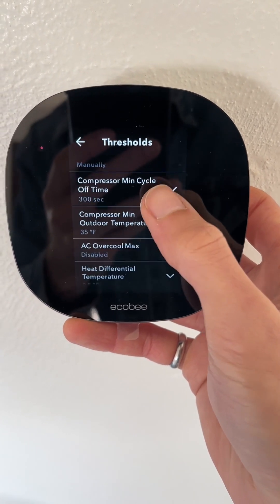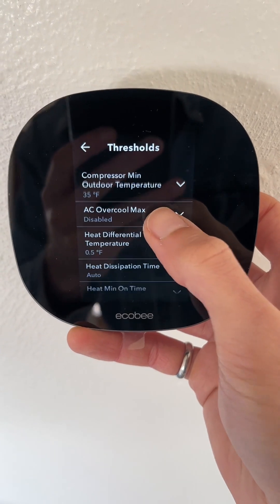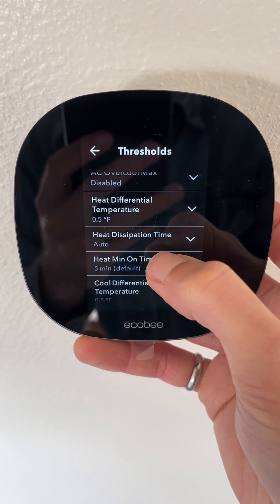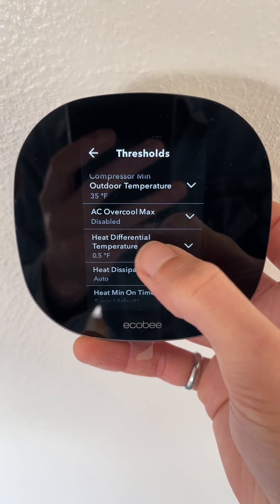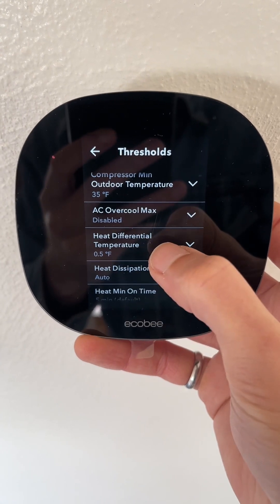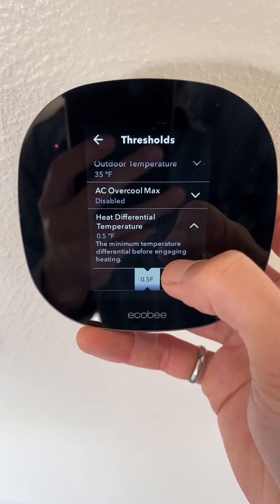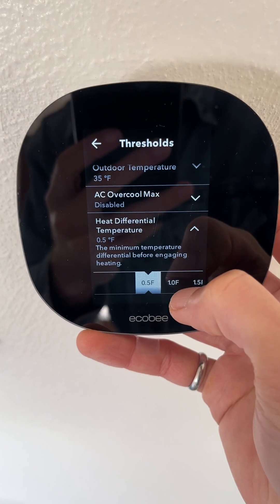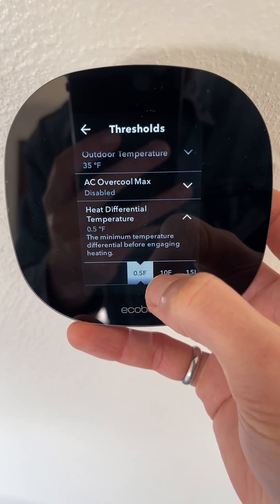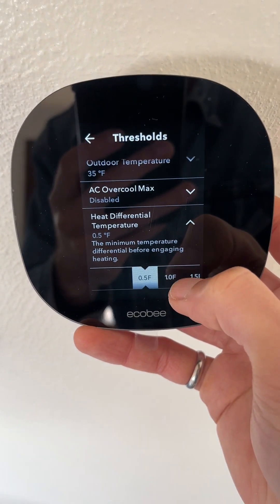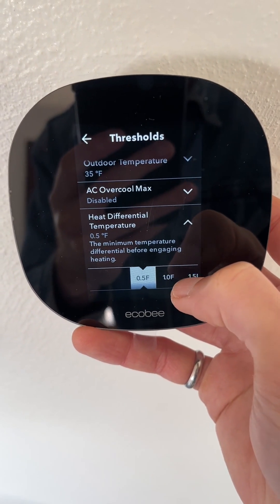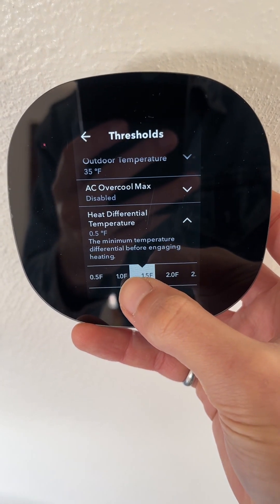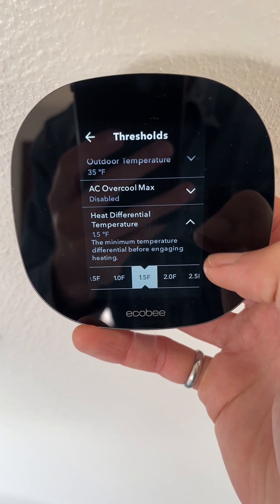Configure Staging on the Ecobee thermostat — we want to set that to Manually. This is essentially going to allow us to determine how we want the furnace to cycle on and off. What we care about right here is Heat Differential Temperature. It says the minimum temperature required before engaging heating, and it's set to half a degree Fahrenheit. That is a really high bar, so I'm going to move it down to one and a half degrees.